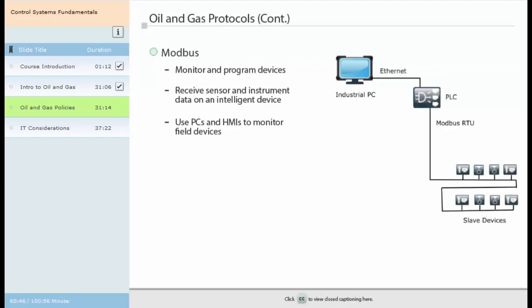The Modbus protocol supports communication between master-slave, client-server applications and intelligent devices. Modbus is used by hundreds of vendors to transfer discrete, analog, input-output and register data between control devices. Modbus oil and gas controllers have the ability to access master-slave applications in order to monitor and program devices, receive sensor and instrument data on an intelligent device, and use PCs and HMIs to monitor field devices.